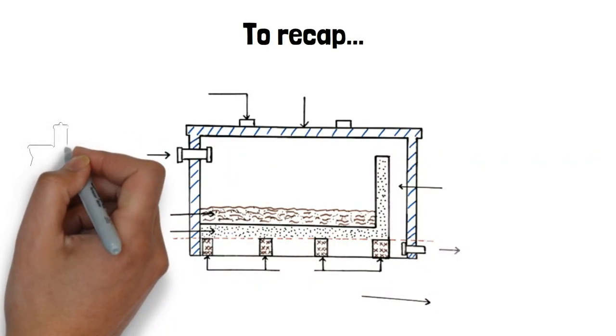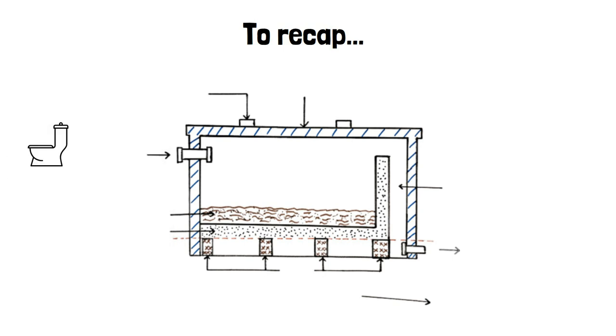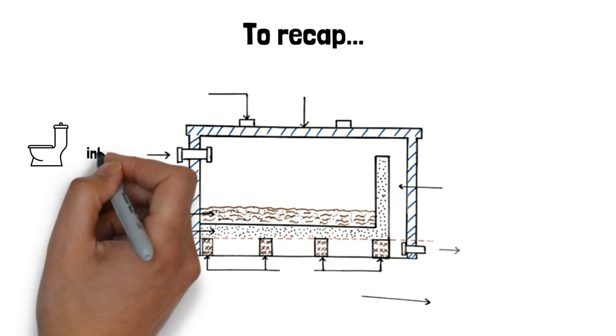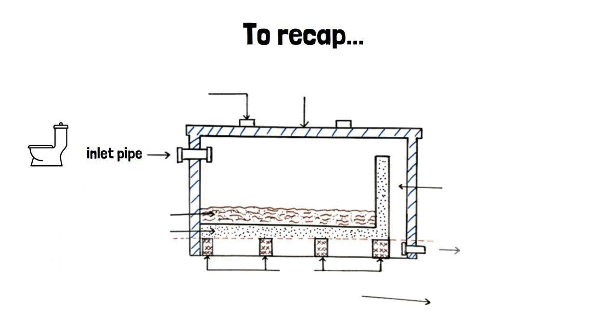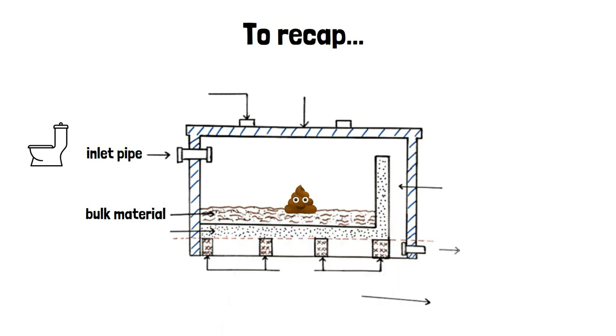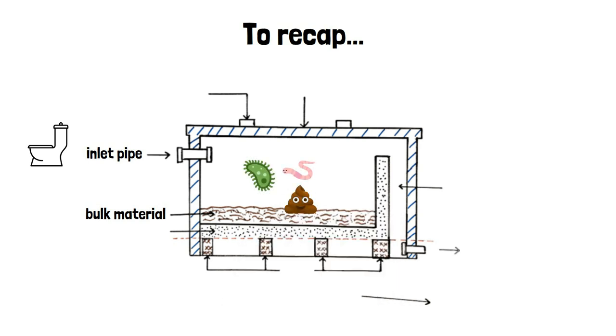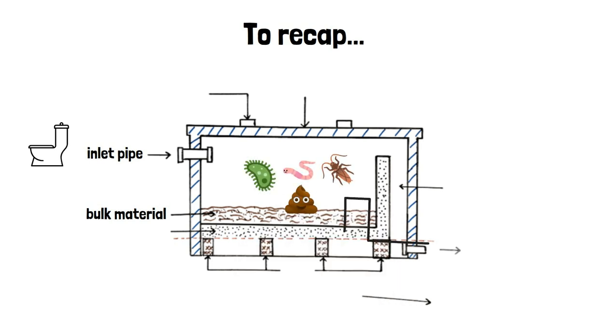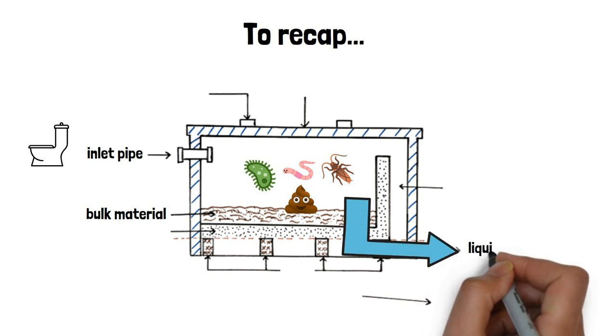So, to recap this section, after flushing your toilet, your black water enters the biodigester through the inlet pipe. It lands on the bulk material, where the solids are trapped and digested by the bacteria, earthworms, and cockroaches. The liquids flow downwards through the filter layer to the concrete beams towards the outlet pipe.